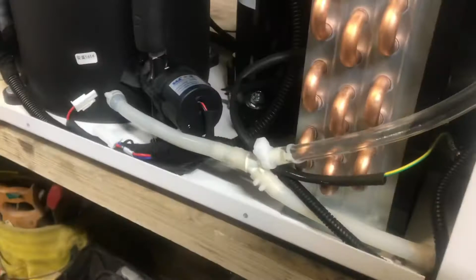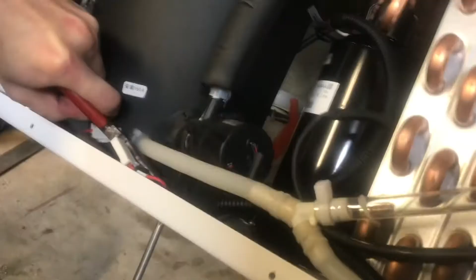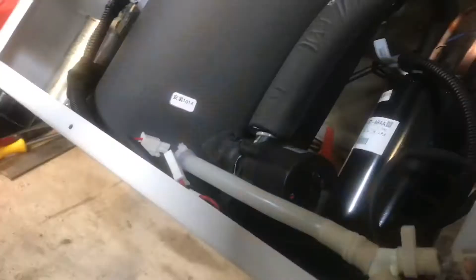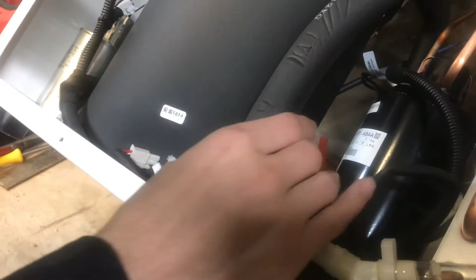I'm going to remove the two screws that attach this motor on. Next, you want to pull up this rubber insulation so you can expose it. There's two zip ties to cut. There's a little bit of glue if it's an original motor, but there's no barbs, so it comes off pretty easily. Just carefully work off this foam insulation and then cut the zip tie closest to the water pump.